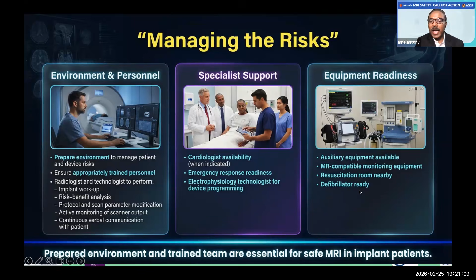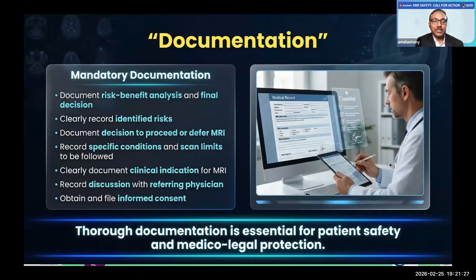especially when we are dealing with cardiac pacemakers and other ICDs: cardiologist availability, emergency team in position, and as emphasized, electrophysiology technologists for resetting the equipment. And also more importantly, MR compatible monitors should be there. The resuscitation room should be just adjacent to the MRI suite, and a defibrillator should be at hand. So I don't have to emphasize much on this. Documentation is very important, starting from the risk-benefit analysis and the details of the implant. All of this has to be clearly documented because it carries a lot of weight, if at all something happens to the implant or to the patient.